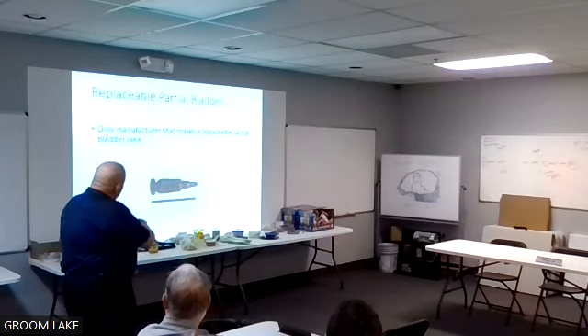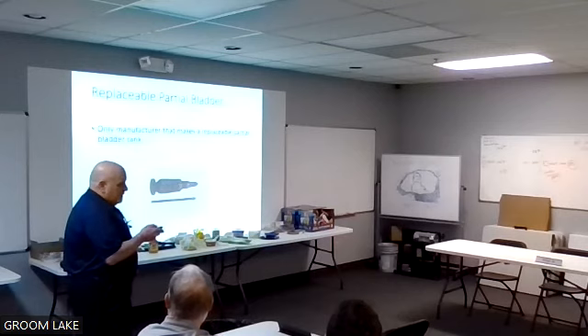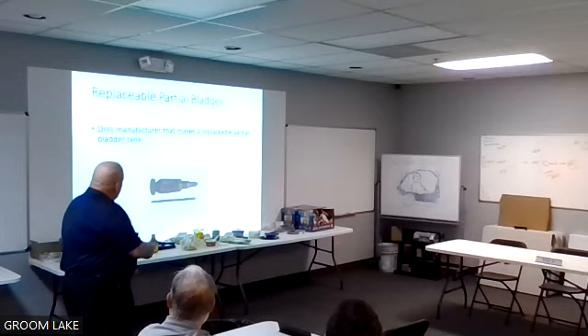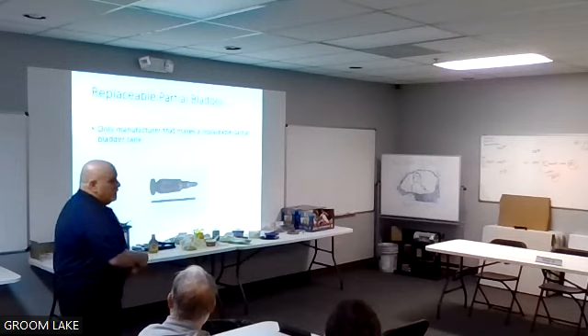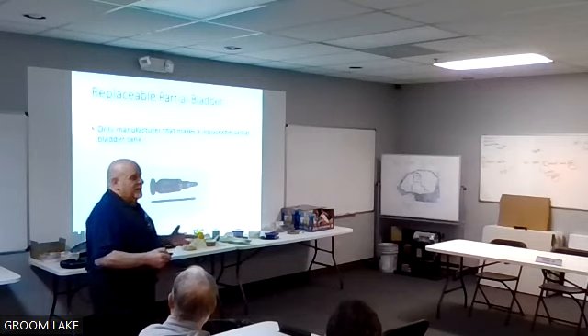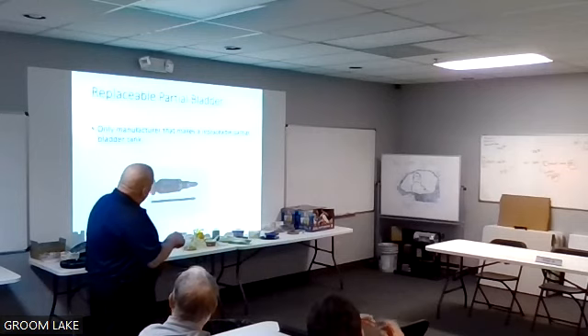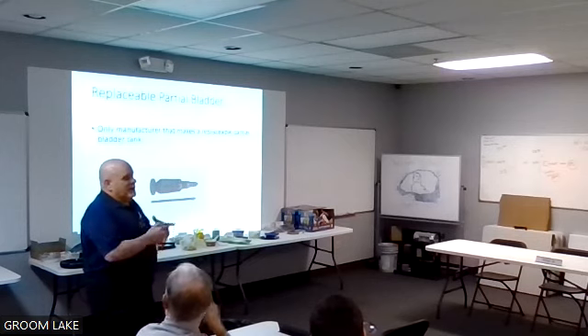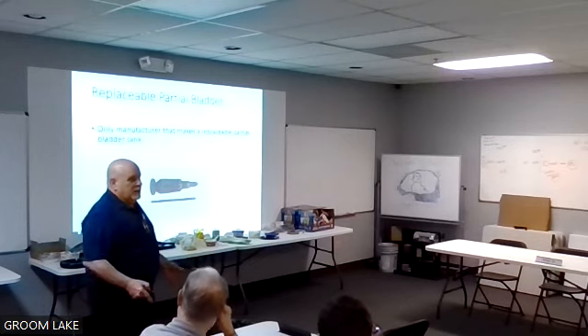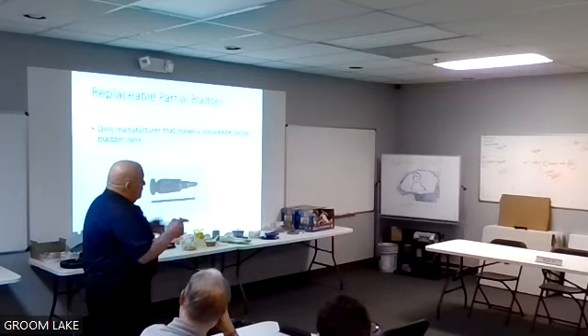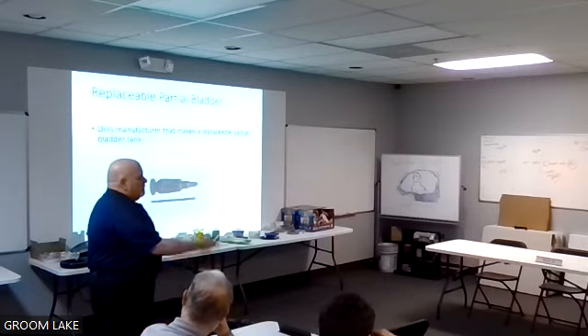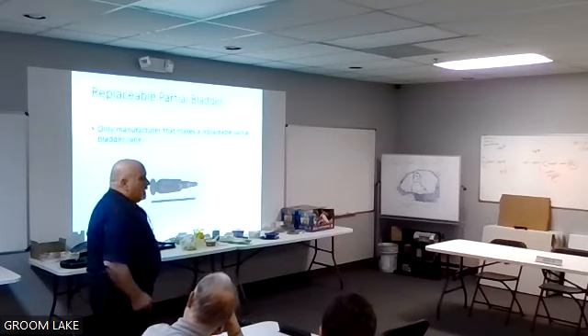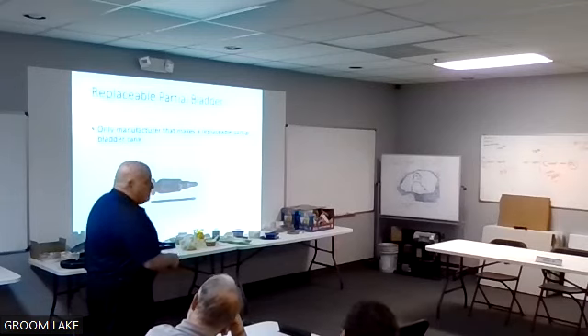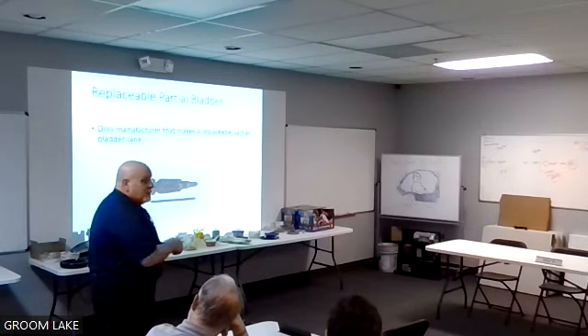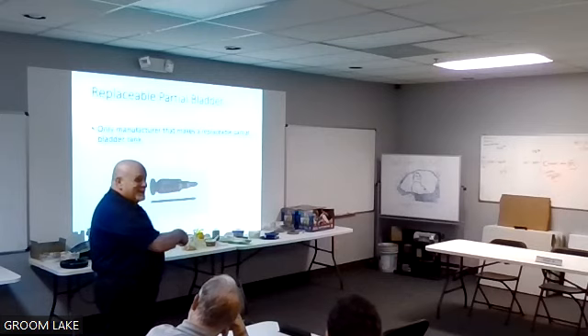This is what the inside of a partial expansion diaphragm looks like. This might be a 45-gallon tank and this bladder may only hold 15 gallons. But again, this bladder inside the tank has to be big enough to take your expanded water volume, which you can calculate. So once you do the calc, it'll say I've got 12 gallons of expanded water, but I need a 34-gallon tank. You go to the partial bladder expansion tanks. Okay, this tank's got a 15-gallon acceptance with a 34-gallon for air. I can use that tank.